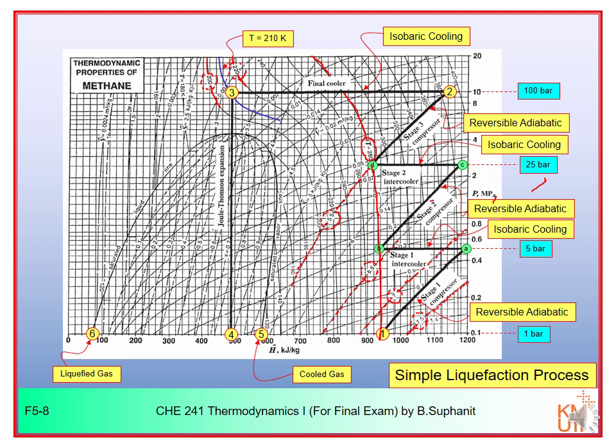After the cooler, the gas is flashed through the expansion valve. For JT expansion, enthalpy is constant, so you move vertically from point three down to point four at 1 bar — the flash drum pressure. At point four you have entered the two-phase region. The liquid product is at number six and the remaining vapor exits at number five.